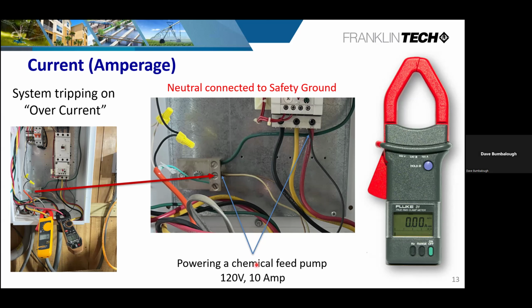The other dilemma we end up with here is we've got leakage voltage. The leakage voltage is coming because the neutral wire and the safety ground are going over here and connecting to the safety bus. So we're actually putting that AC voltage, as it goes alternating back and forth, on that chemical feed pump. It's actually affecting our safety ground. Okay, so if we were to separate that or have some kind of issue, we could get electrocuted. We could get shocked because the chemical feed pump, if it's running, is using that alternating voltage through the safety ground, which is bad news. There should have been a neutral brought over.